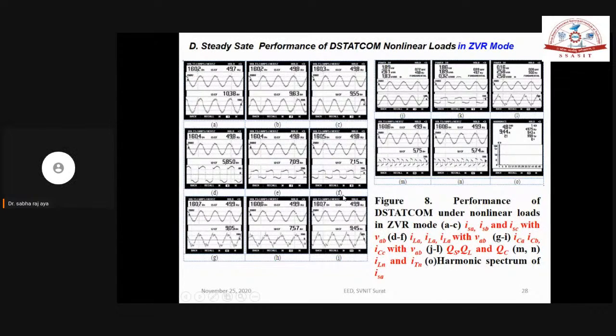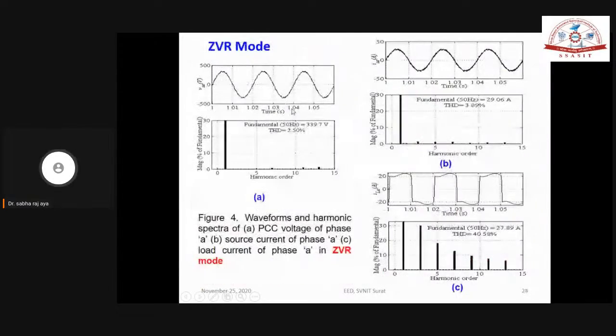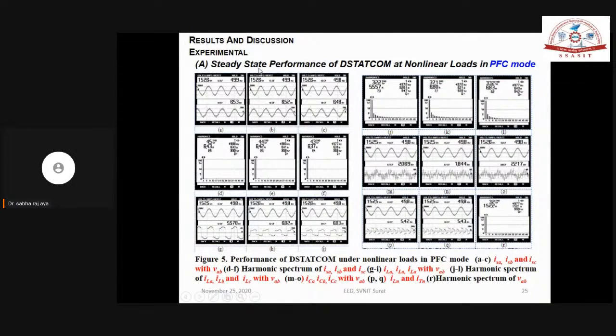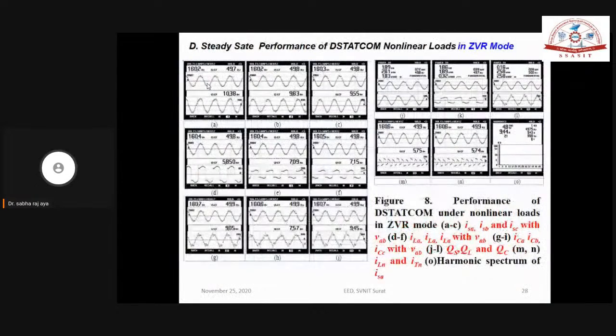Now you can see, this is ZVR mode. In PFC mode, what have we done? In PFC mode, our voltage has reduced to 152. But we have taken a no load of 160 only. So we are able to maintain 160. After compensation, here you can see always we have a leading power factor. See figure J, 1.83 kVAR leading. This much power we want to compensate the voltage from 152 to 160. 8 volt grid voltage we have compensated.